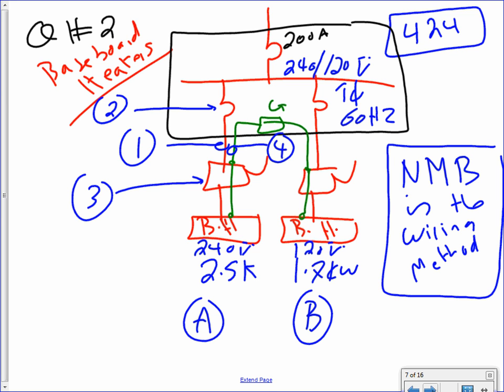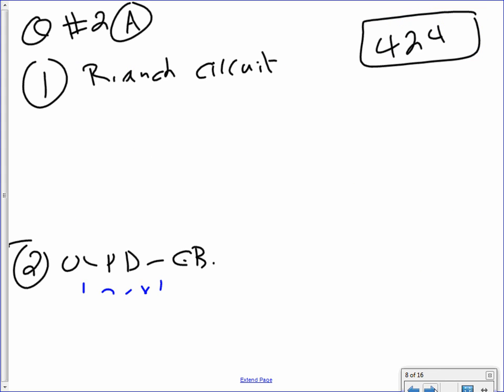For baseboard heaters, guys, the disconnect could be the switch on the baseboard heater, the thermostat, that acts as a disconnect. So you don't have to have a big blown disconnect like for the AC units. Look at the sizes. They are 240, 2.5 kW, 120, 1.7 kW. These are typically the sizes that we use in dwellings. We don't use 10 kW, smaller sizes. Shall we go ahead and start sizing? Everybody knows what we have before we start? Karen, good? Okay, now let's go ahead and start sizing the following.